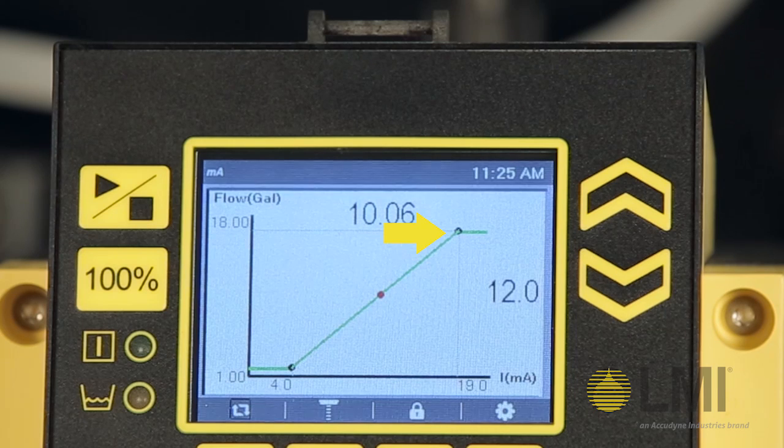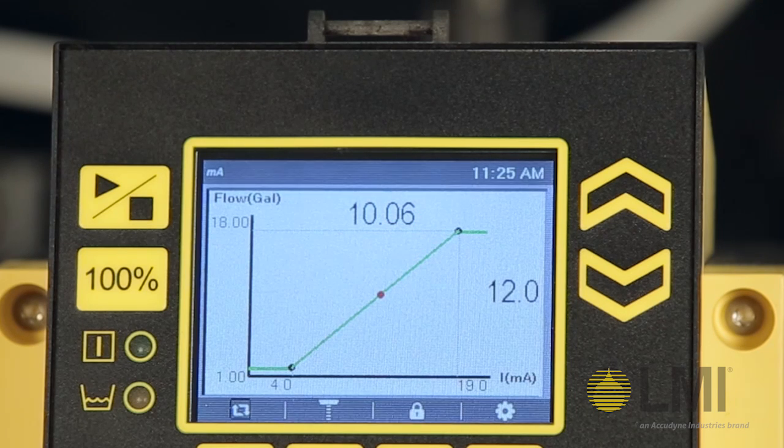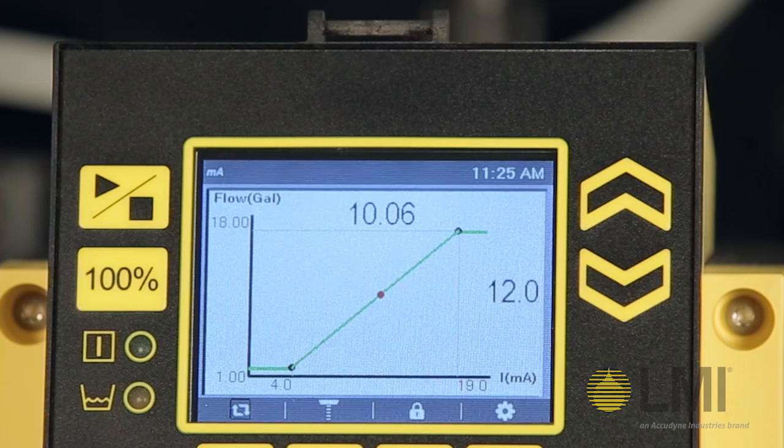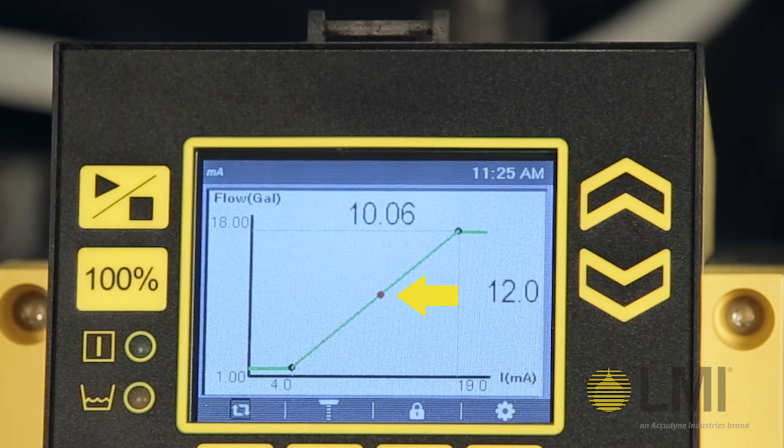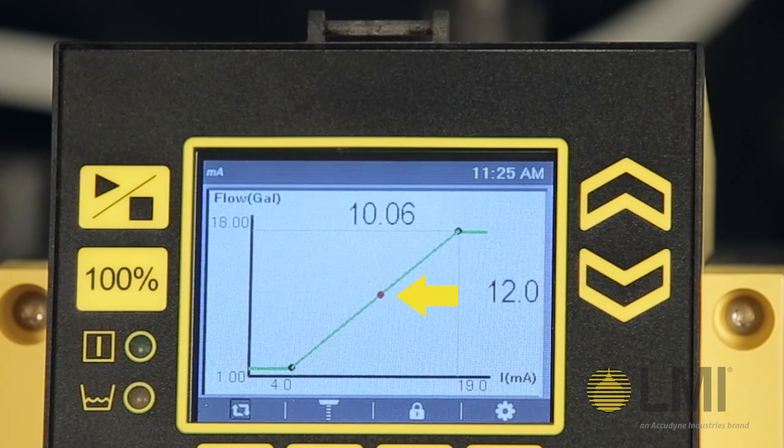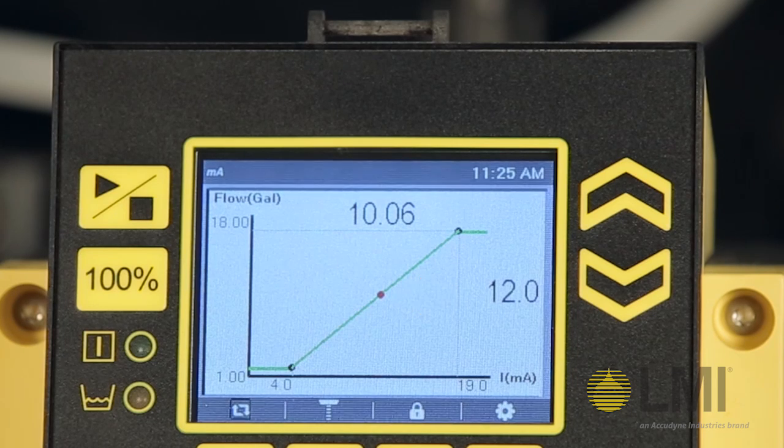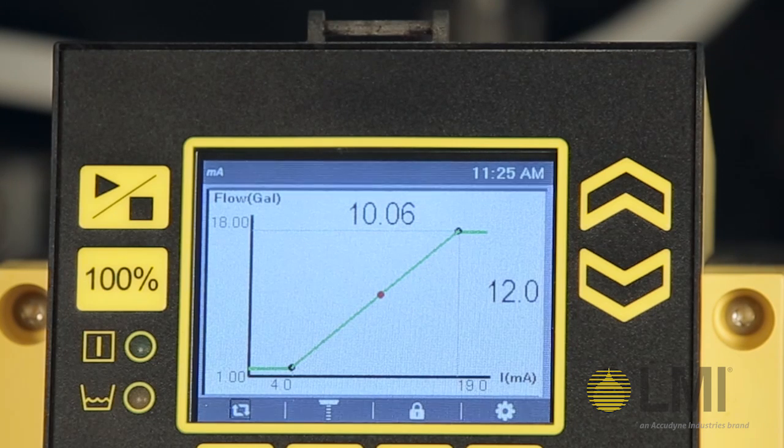At any given input current on the x-axis, you can plot and see what your flow rate will be for the output of the pump. The red dot indicates our current rating, so the pump is at a 12 milliamp signal, which corresponds to a 10 gallons per hour flow rate.